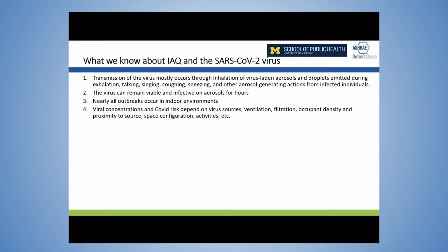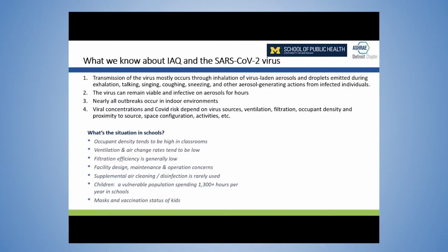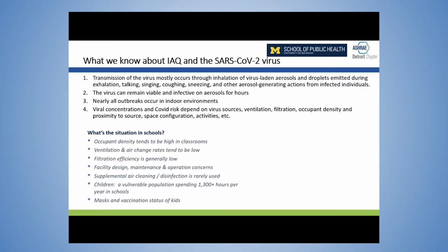So what's the situation in schools, in Michigan schools and other schools? Quickly, we have high occupant densities. We have issues with ventilation and air change rates tend to be low. Filtration efficiency is generally pretty minimal. There are significant concerns regarding the design, the maintenance, and the operation of mechanical systems. Rarely do we see supplemental air cleaning used.